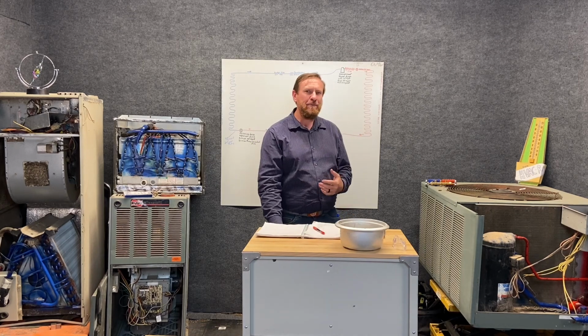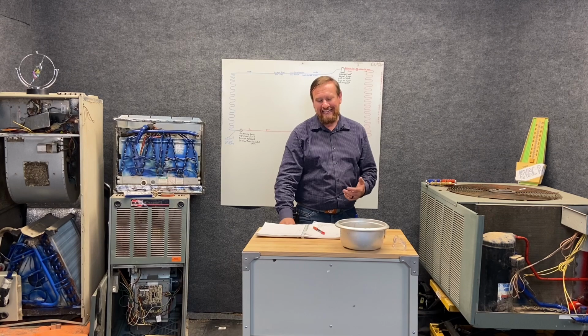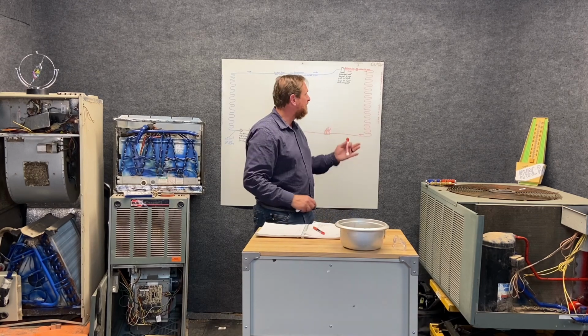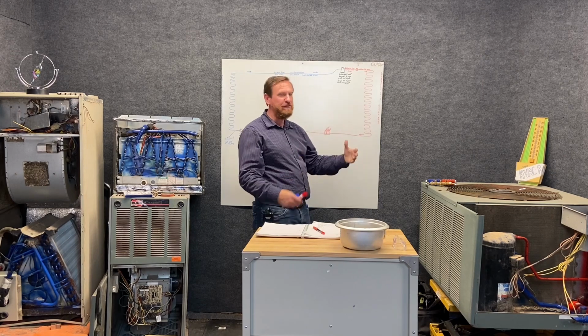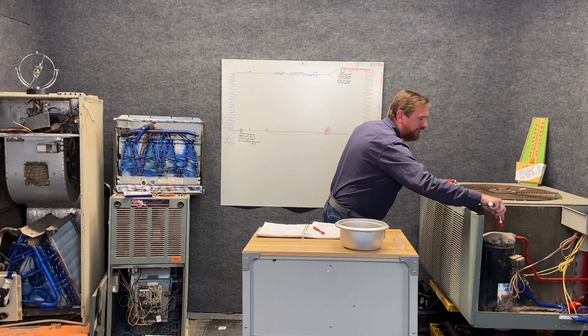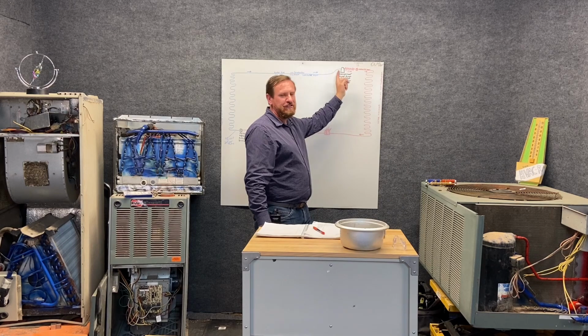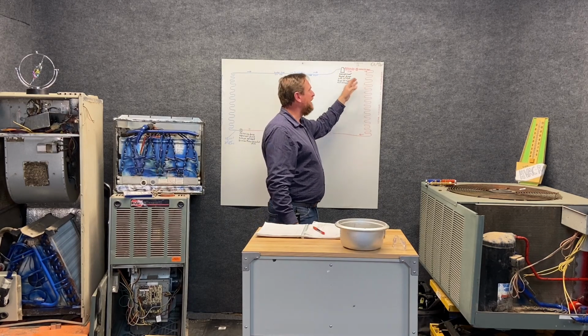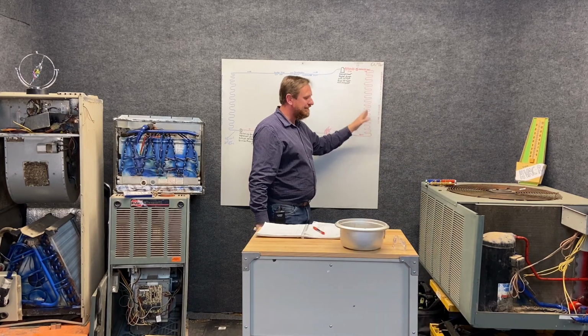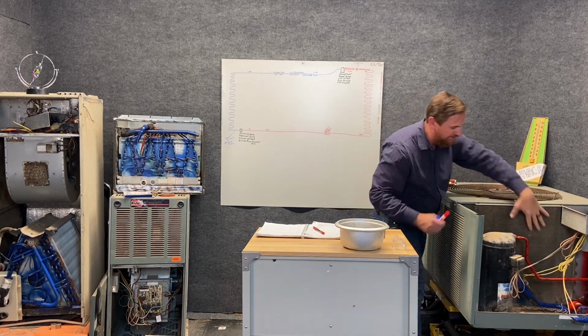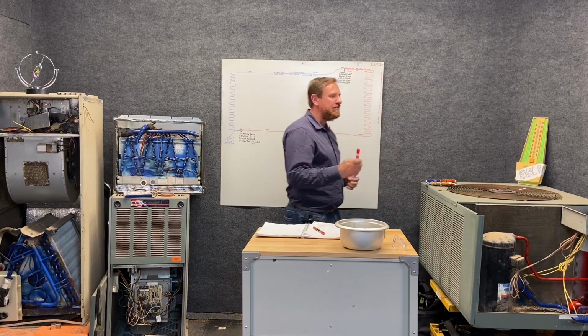So we learned about evaporation and condensing. We're going to add that to our map we already have. So we have our compressor, vapor pump, sucks low pressure vapor, pumps high pressure vapor, moves the refrigerant. That's our compressor here. Then we have our discharge line, also the hot gas line, high temperature, high pressure, superheated vapor. That's this line right here. Then we end up in our condensing coil. So all of this is our condensing coil. That's what we're going to talk about first.